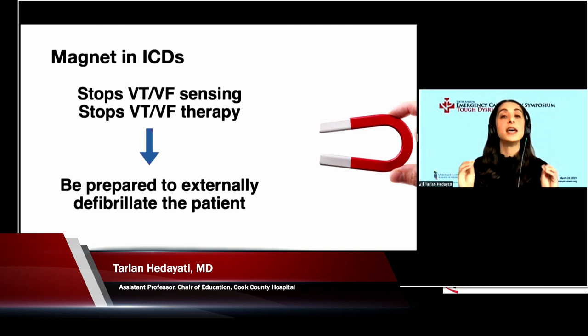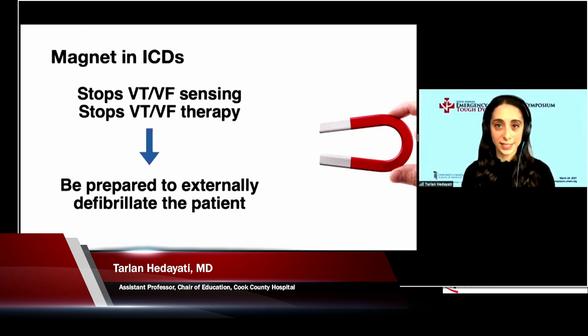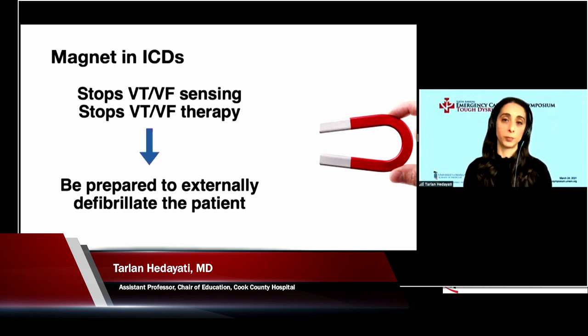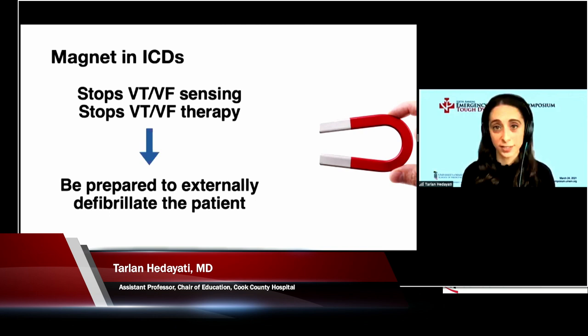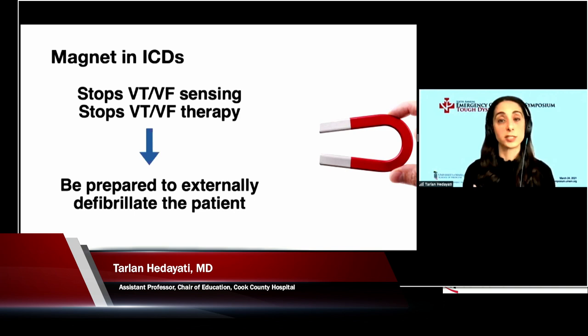The problem with turning off the sensing function of the ICD is that the cardioversion-defibrillator portion will no longer detect dysrhythmias—it won't see VTAC or VFib. If it can't see those dysrhythmias, it won't cardiovert or defibrillate. So you are taking the life-saving function away from the patient when you put the magnet on an ICD. Before you do that, make sure you have external defibrillation pads on the patient, then put the magnet on. You have to be prepared to externally defibrillate them yourself when you turn off that sensing function.